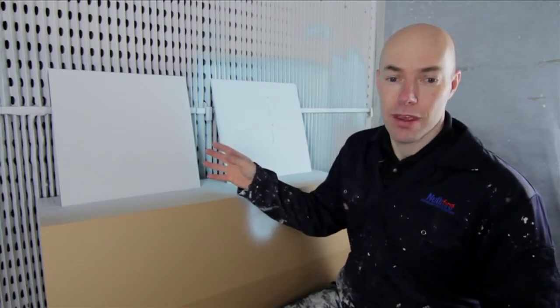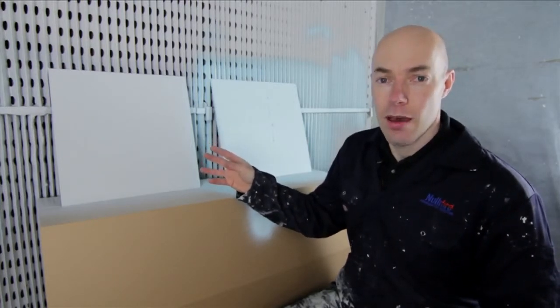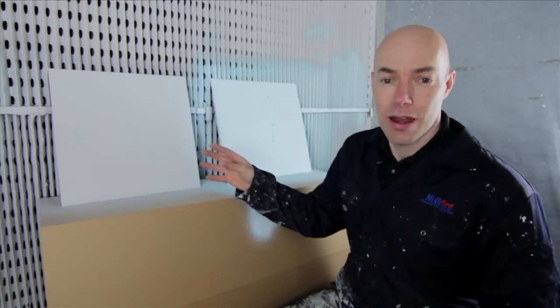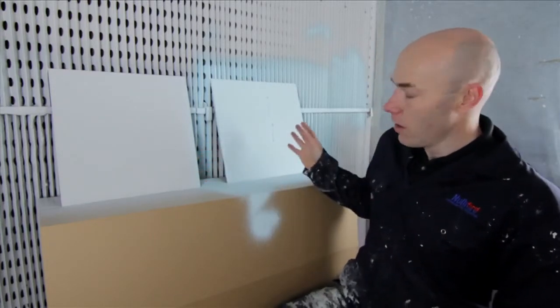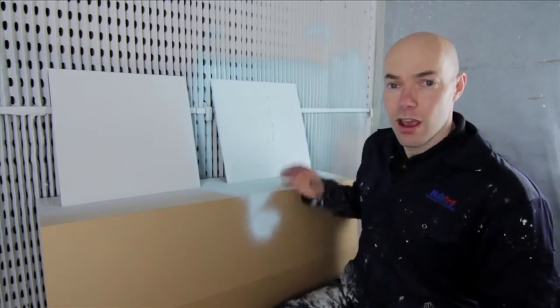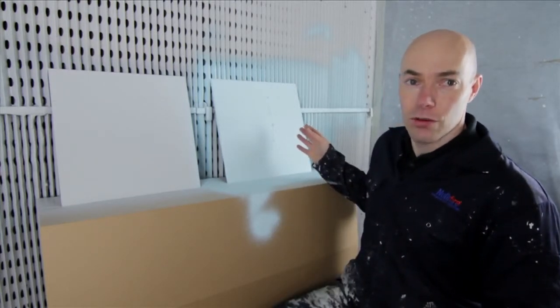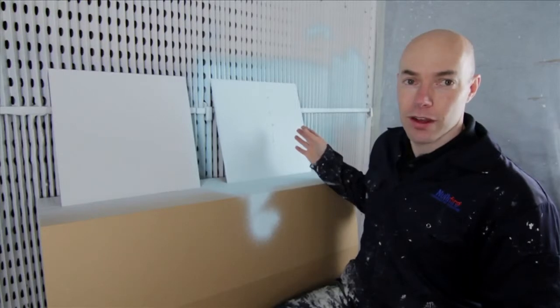The S707-120, 1.2mm wet film thickness is a typical build but that's very much the upper limit of current water-based intumescence. In comparison the SC900 range goes well beyond those limits and takes us up to 4mm wet film thickness.